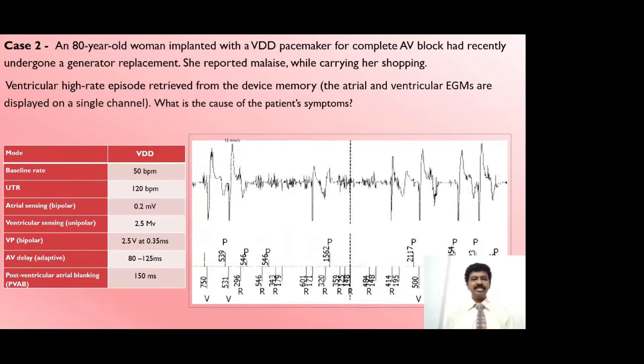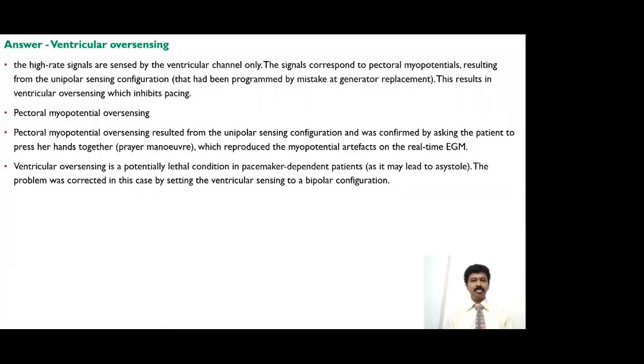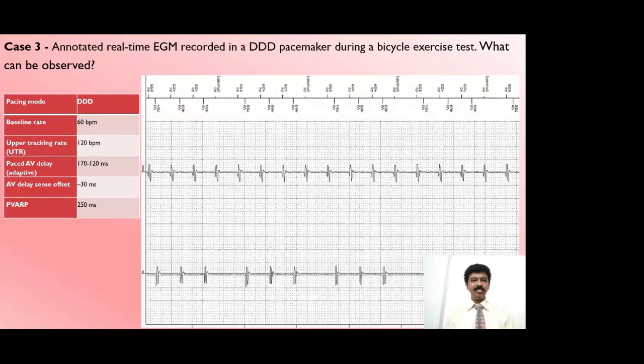So again, this is a sensitivity issue. You can see that myopotential sensing, oversensing, leads to inhibition of the pacemaker, causing symptoms. So again, this could be due to high sensitivity thresholds and unipolar programming. That can be avoided by changing to bipolar programming and keeping the sensitivity lower.